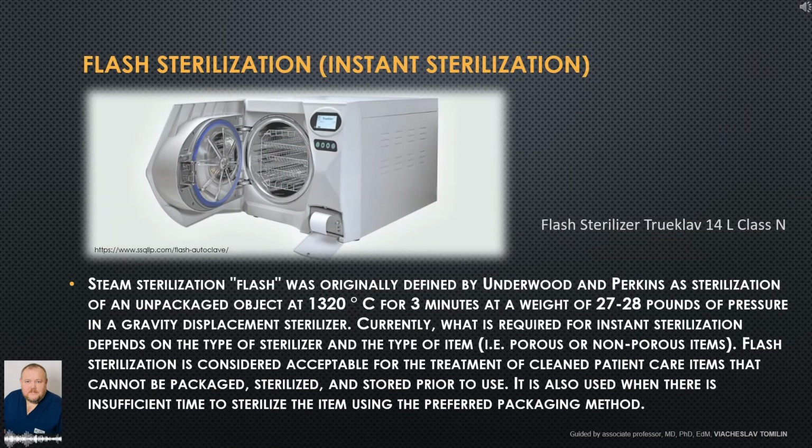Flash sterilization. Instant sterilization. Steam flash sterilization was originally defined by Underwood and Perkins as sterilization of an unpackaged object at 132 degrees Celsius for 3 minutes at 27 to 28 pounds of pressure in a gravity displacement sterilizer.